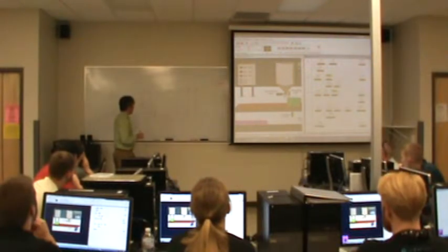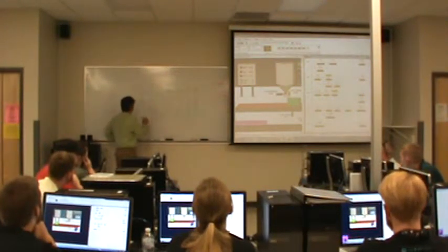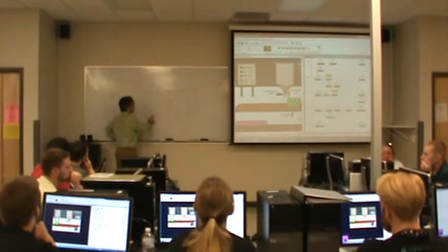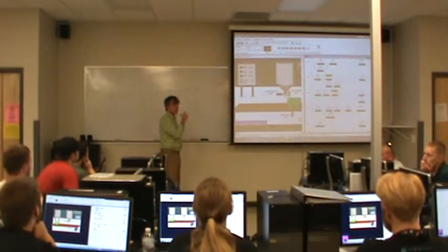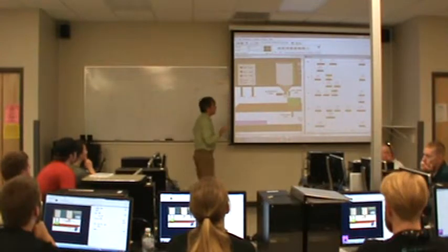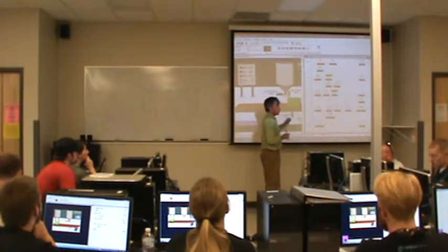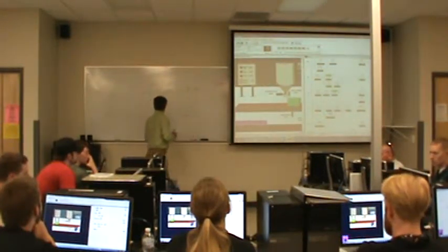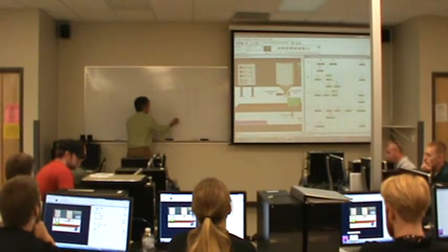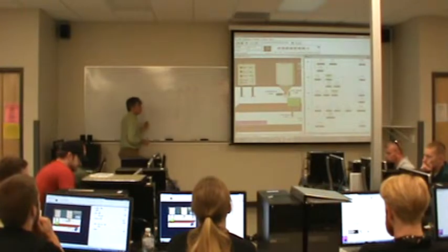All right, I'm sorry, I see I'm running late on time, but let me just finish this quickly and then I'll close it. Okay, so when the full bit is on and prox is true, but level is not true, that's the condition. That's the whole point of adding this bit, right? It's when we remember that a box was full, prox is true, level is not true. What do we want to do? Well, we've got a full box. We don't want to try and fill it. We want to keep the motor moving and leave the valve off. Okay? We are not filling, we have a full box.